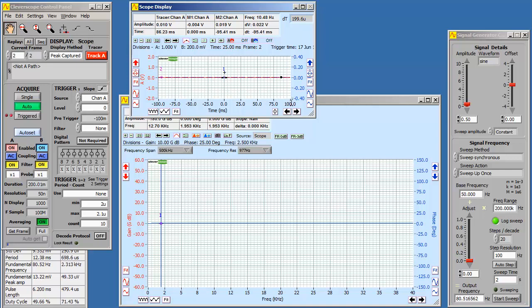All the information in the capture is used, so longer capture times give us better coherence between the measured stimulation and the feedback signals. If you are having problems getting good coherence values, increase the capture duration. We'll talk about this a bit later on. The 200 milliseconds should work just fine.